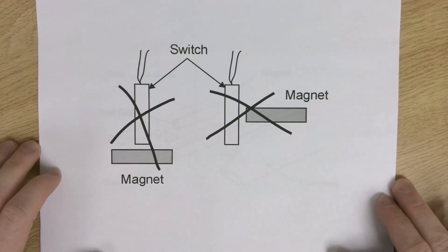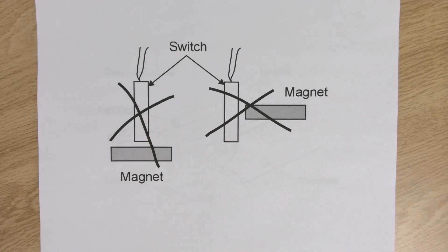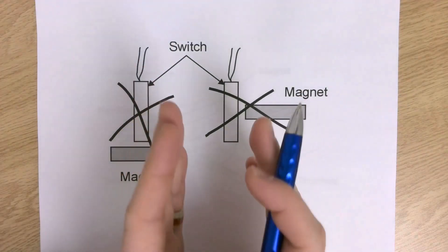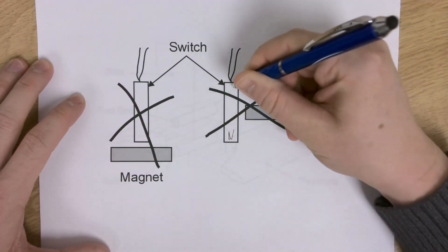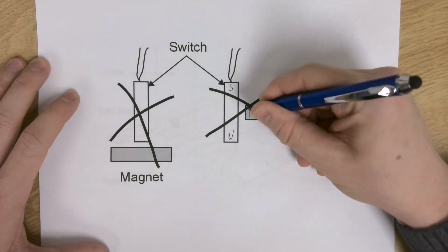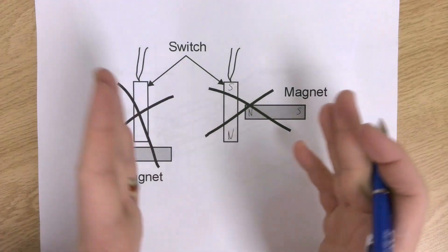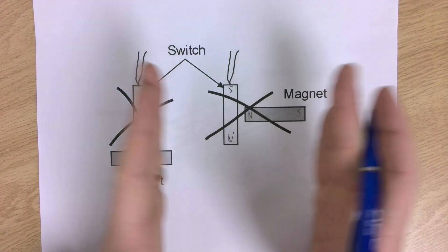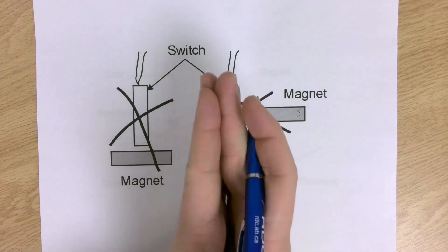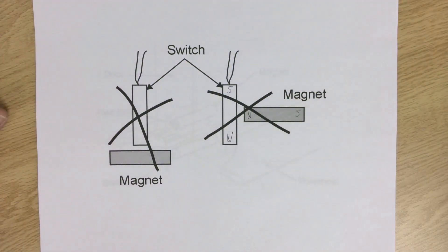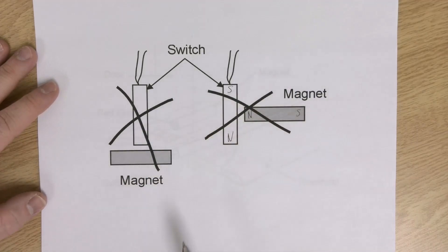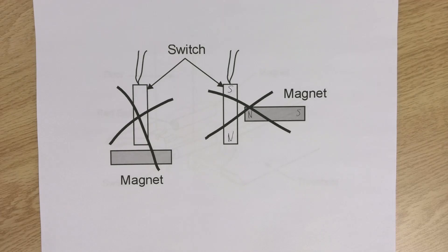The most common failure in an alarm system is usually poor installation. The magnets need to be oriented correctly. If one magnet is North-South and the other is oriented wrong, there won't be enough magnetic lines of flux working in the attraction direction to keep the contacts closed. So the major problem that comes up in alarm systems is usually poor installation.